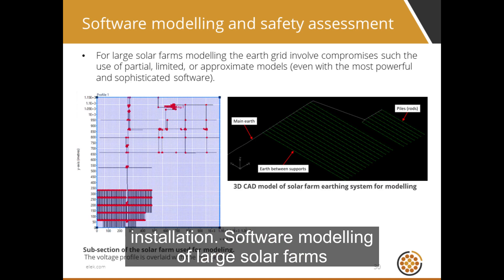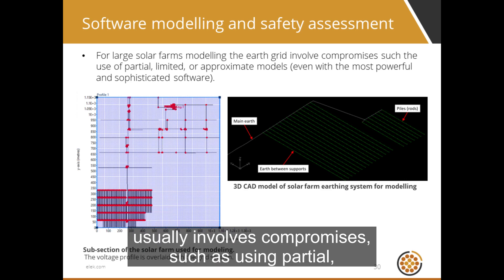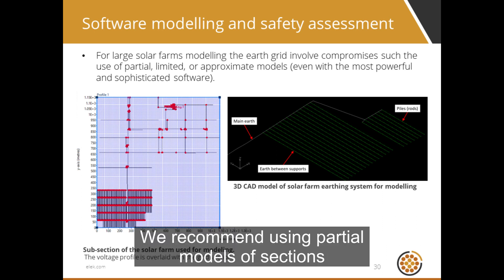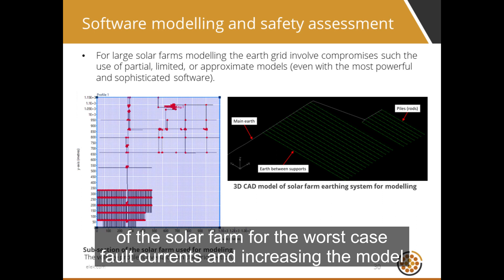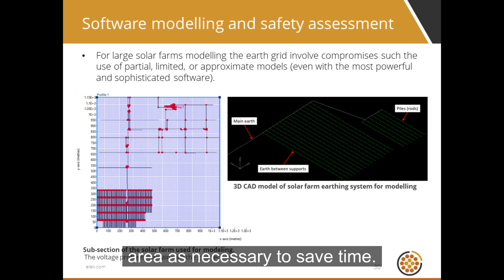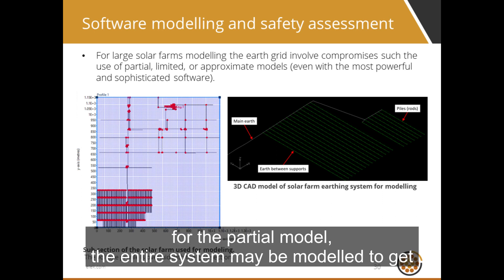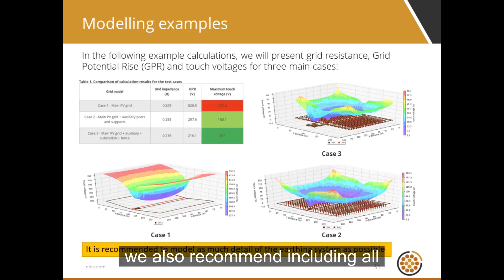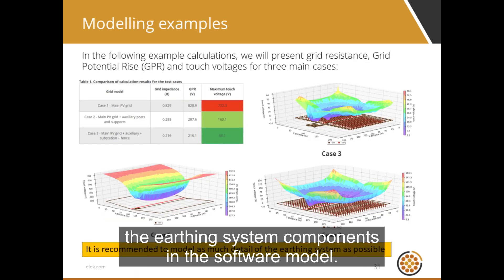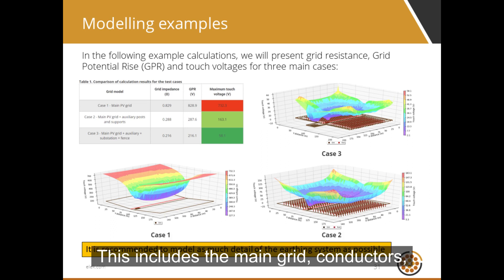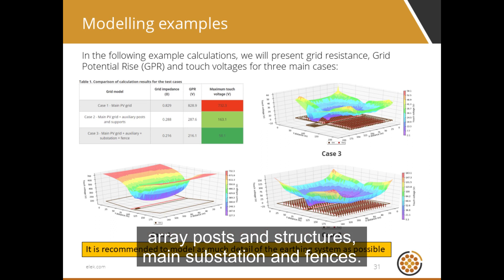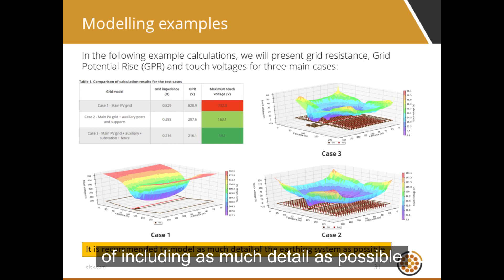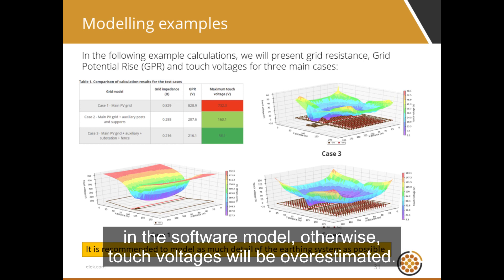Software modeling of large solar farms usually involves compromises such as using partial, limited, or approximate models — the standards recommend this. We recommend using partial models of sections of the solar farm for the worst-case fault currents and increasing the model area as necessary to save time. Once safety has been confirmed for the partial model, the entire system may be modeled to get the overall system performance, which should be better than that for the partial model. We also recommend including all earthing system components in the software model: main grid conductors, array posts and structures, main substation, and fences. The example shown here demonstrates the importance of including as much detail as possible in the software model — otherwise, touch voltages will be overestimated.